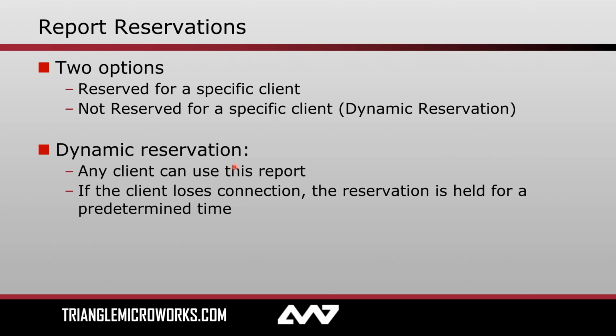Now, a user-defined parameter, resvTms, basically a reservation timeout, will start ticking down. Let's say it's 10 seconds. That report will still be reserved and held for me until that timeout expires. So if communications are restored in that time, no one else can grab it in the interim, and I'm able to receive all the changes that occurred that have been stored in that buffer. So this is not as relevant for unbuffered reports because there is no buffer to store it in.